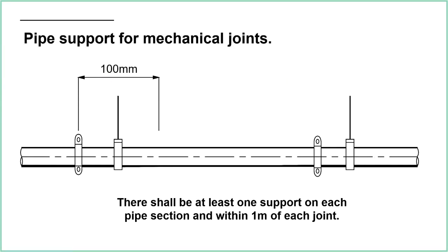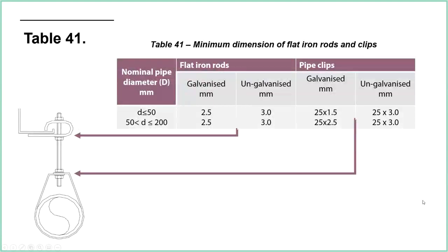And again, what this diagram here is showing is that we've got 2 joins of the pipe, so we need a support between each one, but we also need each piece of pipe to have a support. So if the hanger on the left-hand side was moved more to the left, to the other side of the grooved coupling, then you've got a support within that designated area, but then you don't have the support on that center piece of pipe. So yeah, that's something again to bear in mind. Each piece of pipe is going to need its own support.